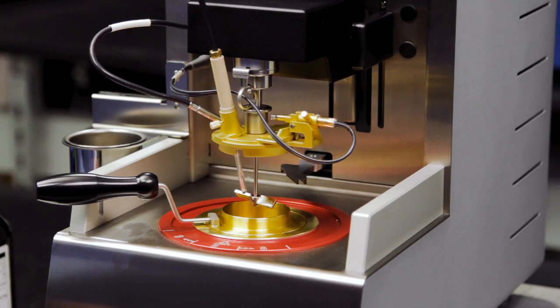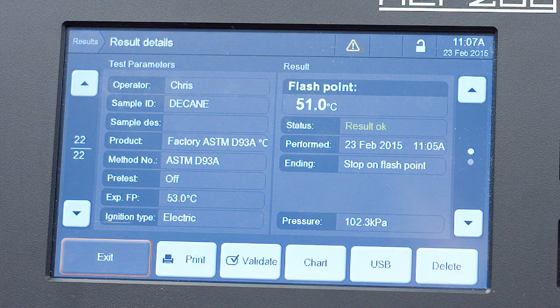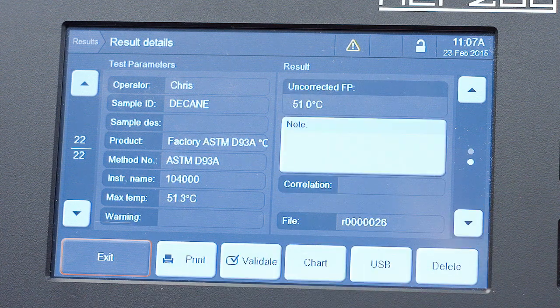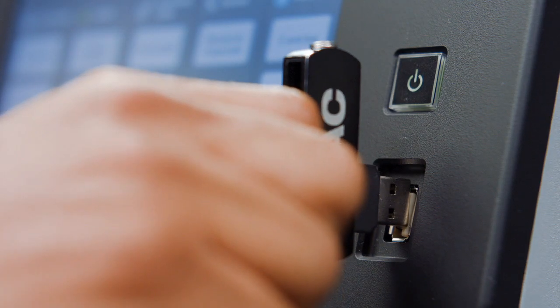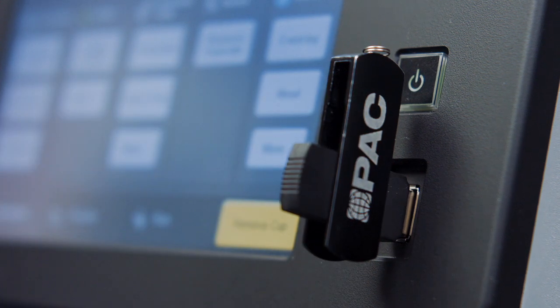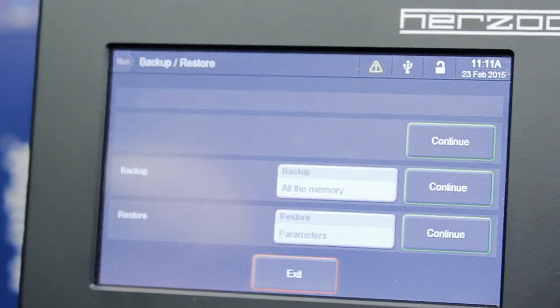OptiFlash also includes an ambient pressure sensor, which enables automatic flashpoint correction for ambient pressure. Its features, like LIMS communication and the USB drive, make it simple for users to export and share data.